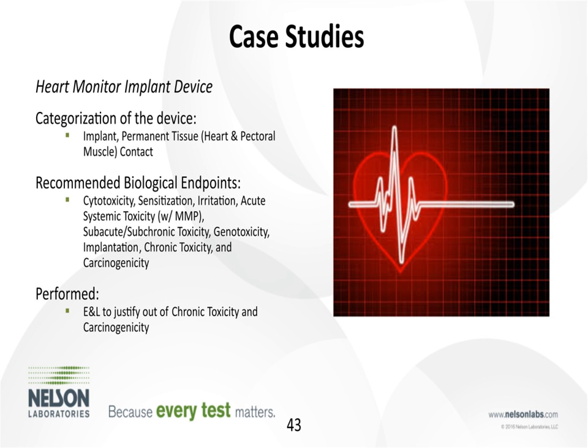They performed all but chronic toxicity and carcinogenicity. We use extractable leachable testing on the device to justify them out of those endpoints.